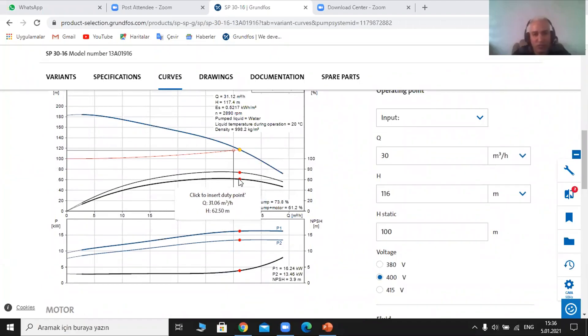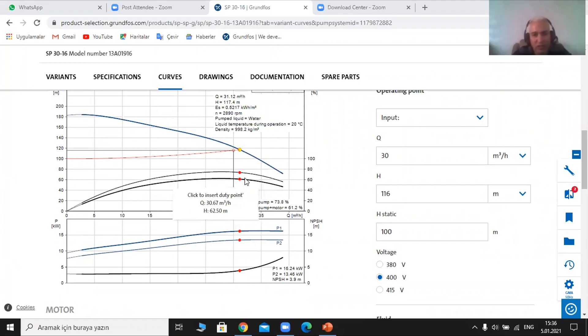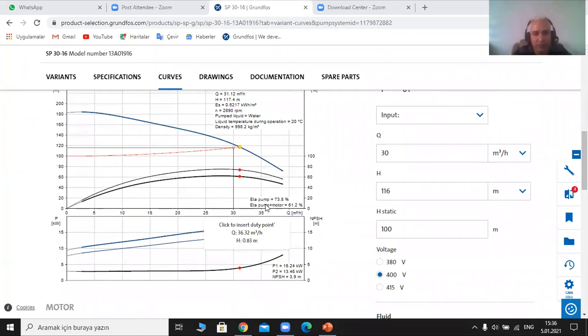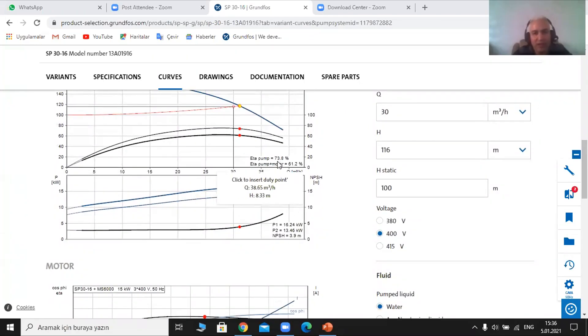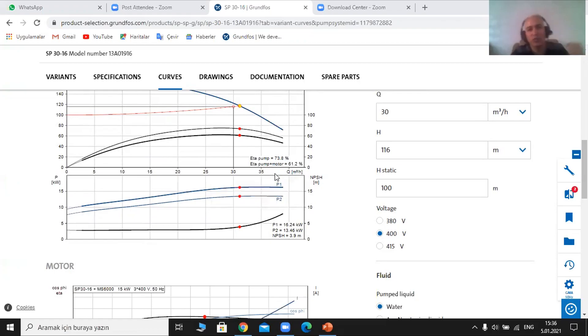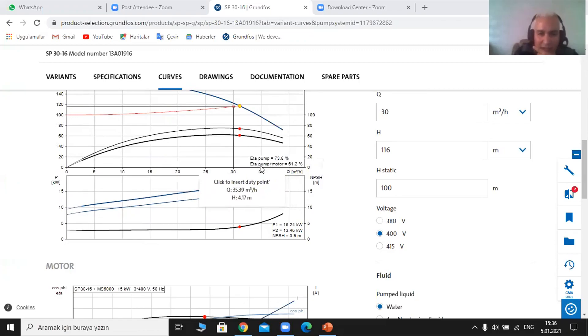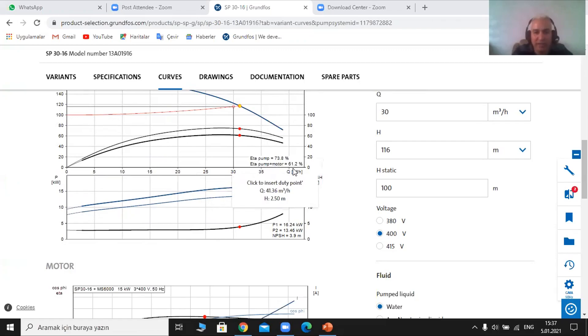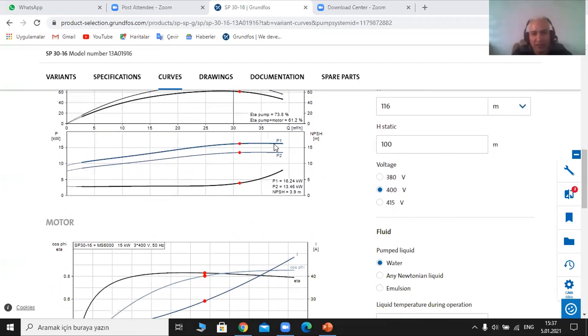The software provides the efficiency for the pump and for the whole system — pump and motor combined. The first value is for the pump: efficiency is 73.8%. Based on this efficiency, I can know how much losses I have and how long the life span would be. The total efficiency for pump and motor combined is 61.2%. For the kilowatt of the electrical motor (P1), it is 16.24 kW.